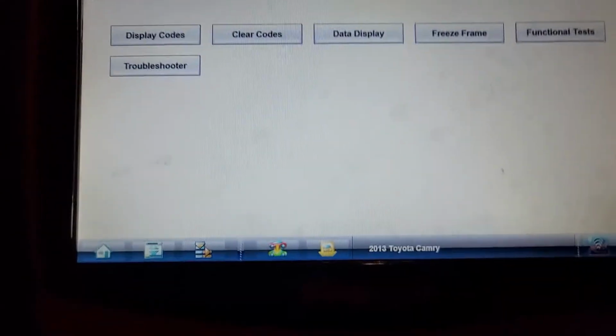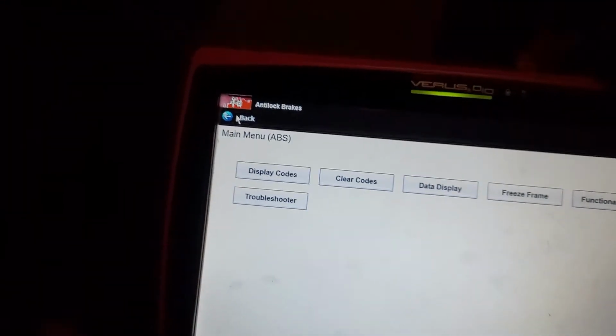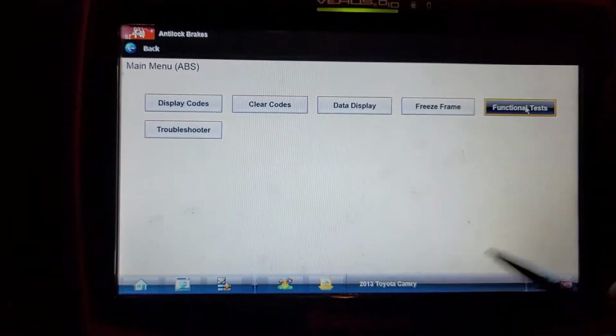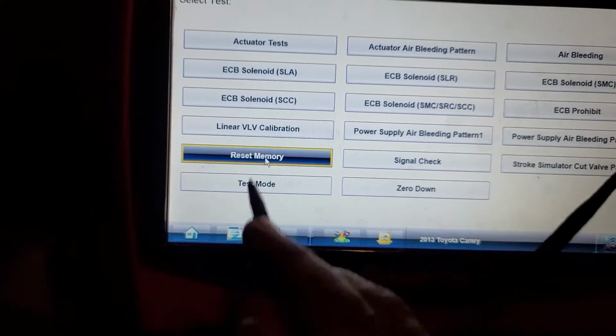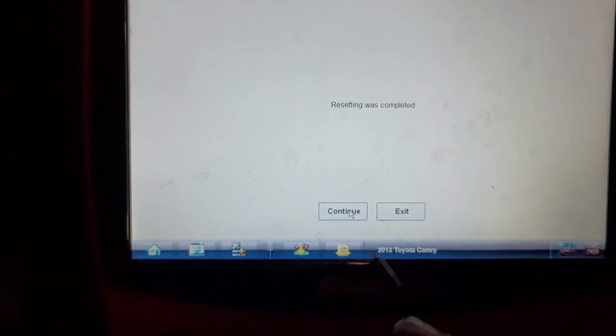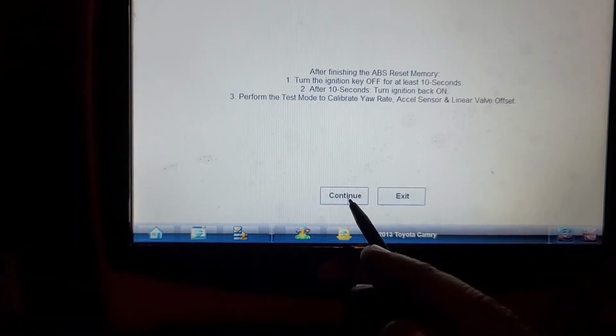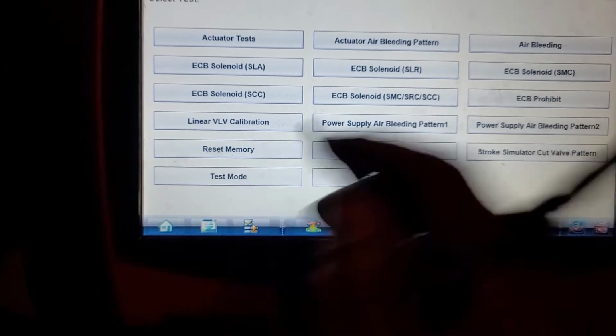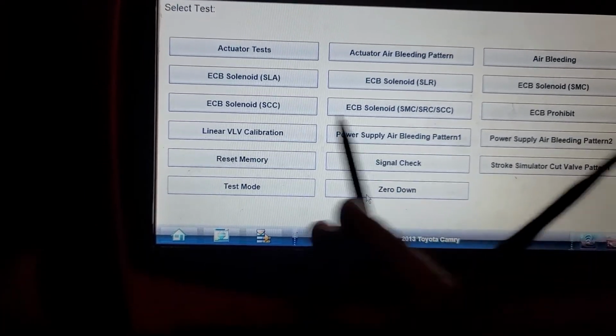Let's go back here, go to function test, first reset memory, yes, continue, complete. Now we're going to perform test mode to calibrate; we can go to linear valve calibration.